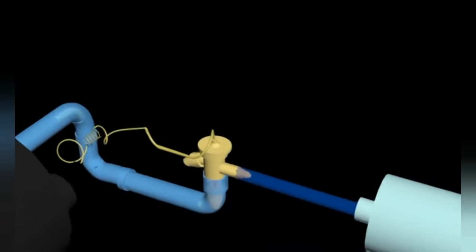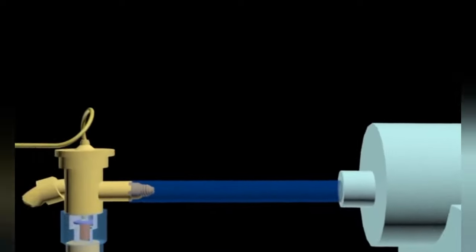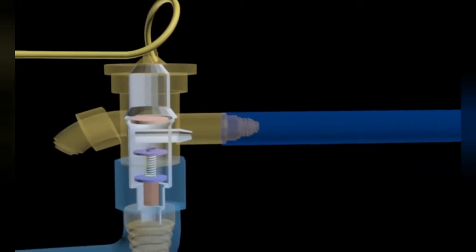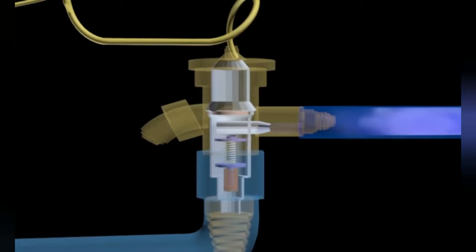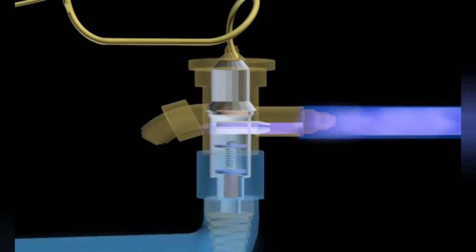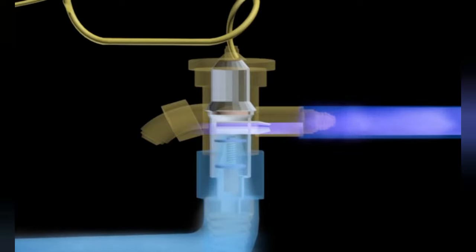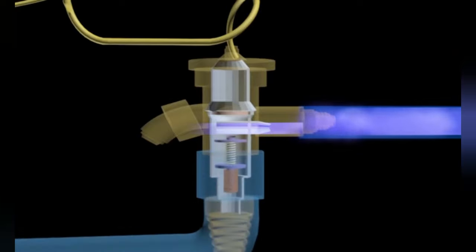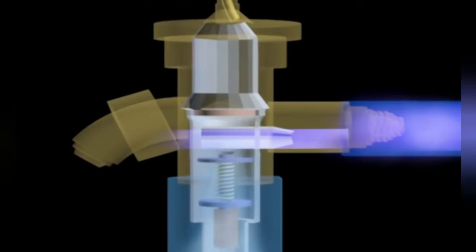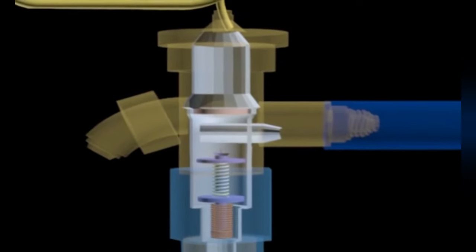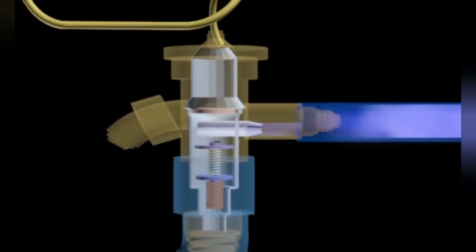The expansion valve serves to reduce the pressure and control the flow of refrigerant going into the evaporator. When the pressure of the refrigerant drops drastically, the temperature also drops dramatically to below the chilled water temperature. In a centralized system, a TXV thermal expansion valve type is used, which operates according to the temperature of the refrigerant coming out from the evaporator.